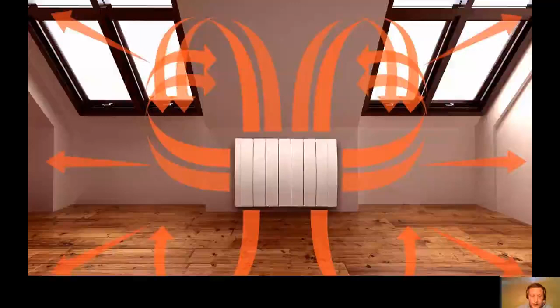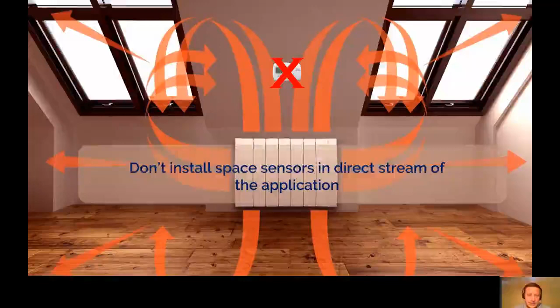Sticking on the where, or moreover where not - this is in a domestic dwelling, and one of the things we still see in the industry, which can be quite annoying if you're wondering why things are getting hot and cold, is you'll see a sensor or a stat directly above the application. The problem with that is, of course, when heat satisfies a set point on a stat, it just keeps going on and off, in and out, and you don't really know why. So sensor positioning is really important for the BMS to operate efficiently.